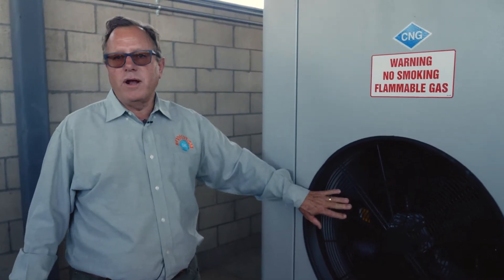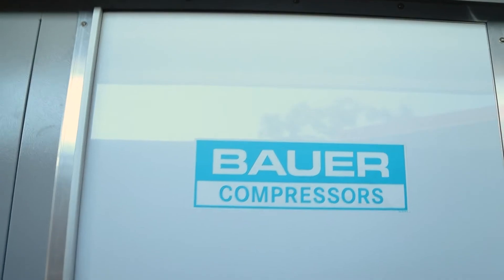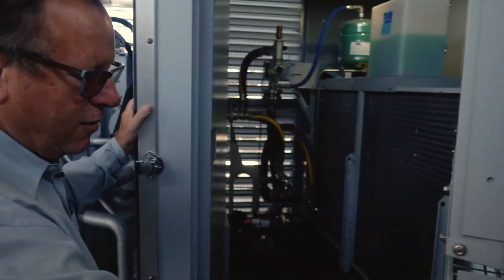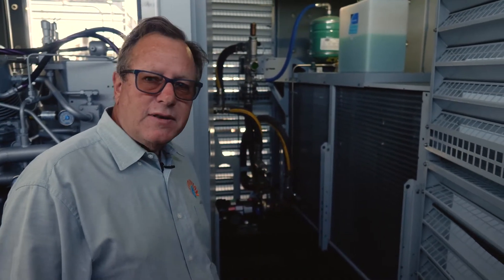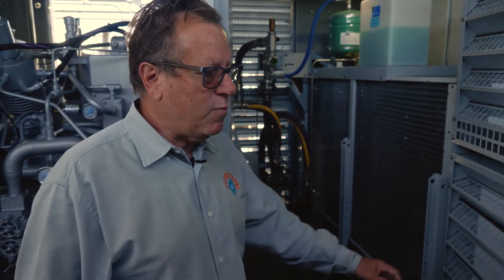The cooling fans on this machine are also on variable frequency drives of their own, which is nice because they don't have to run at 100% all the time. They'll start out running very low and increase in RPM in response to whatever the heat load is on the machine, so quite often they're running at a speed so low that you don't even hear them. This enclosure is separated into two compartments — one houses the compressor itself, the other locates the cooler that supplies the liquid cooling. It's a very well thought out, trouble-free system. We've got about six of these machines installed throughout central California now, and we've had absolutely no trouble with the cooling system.